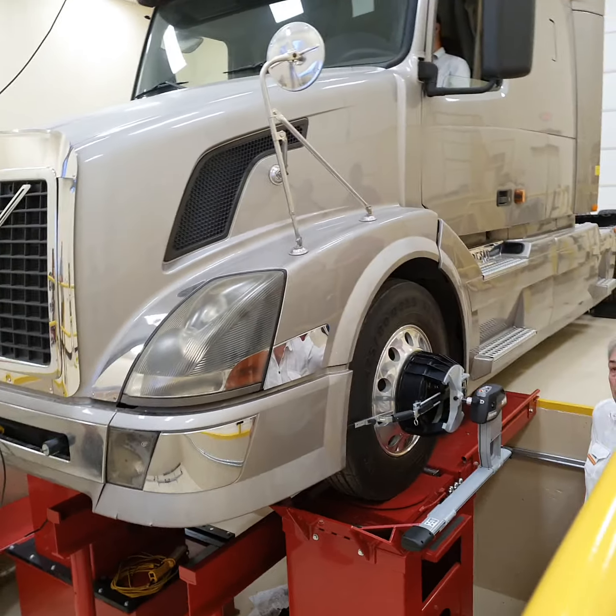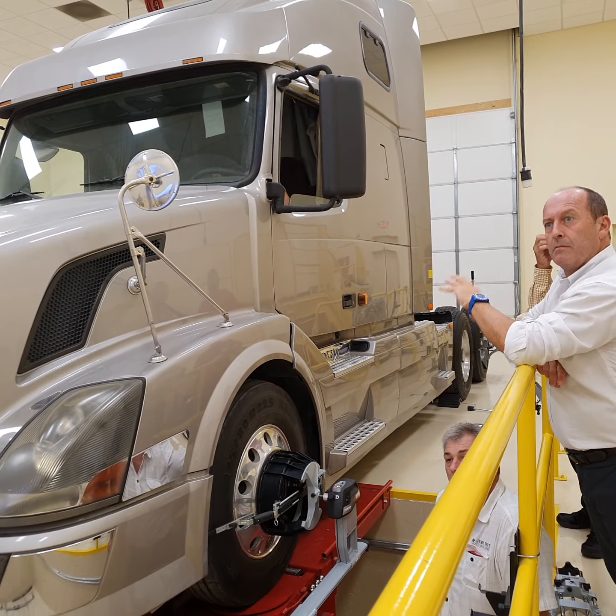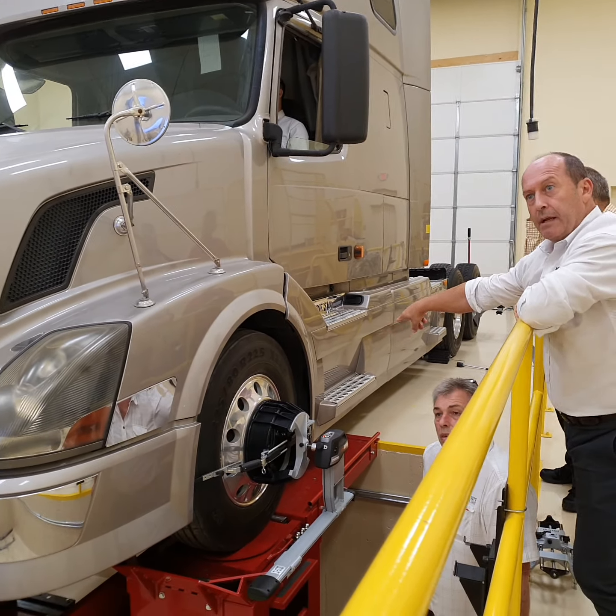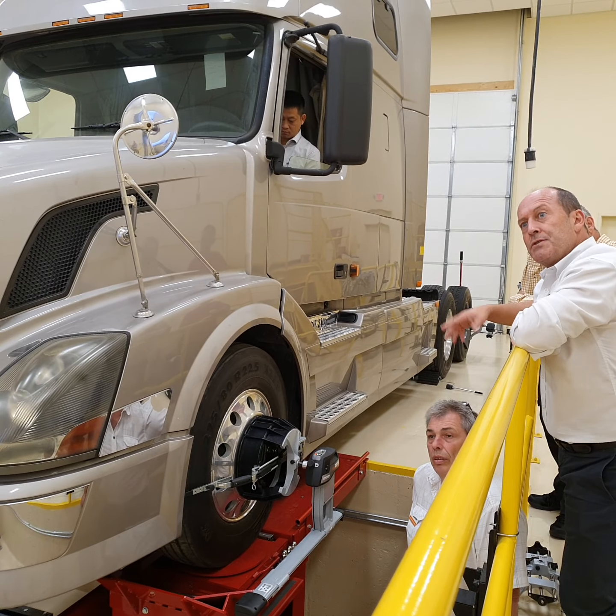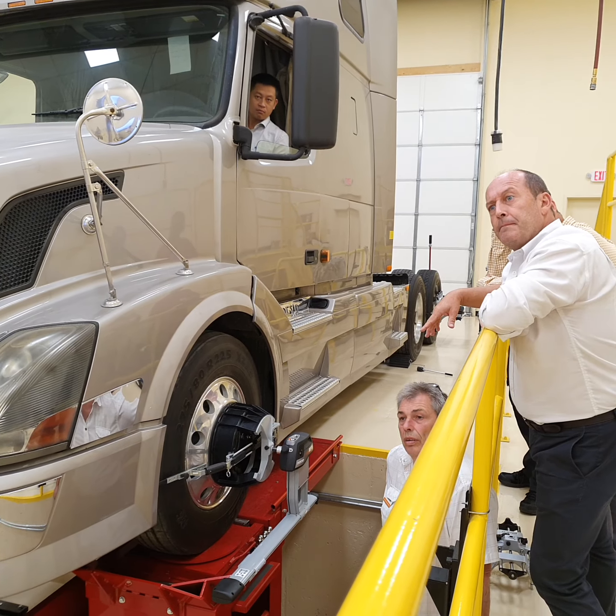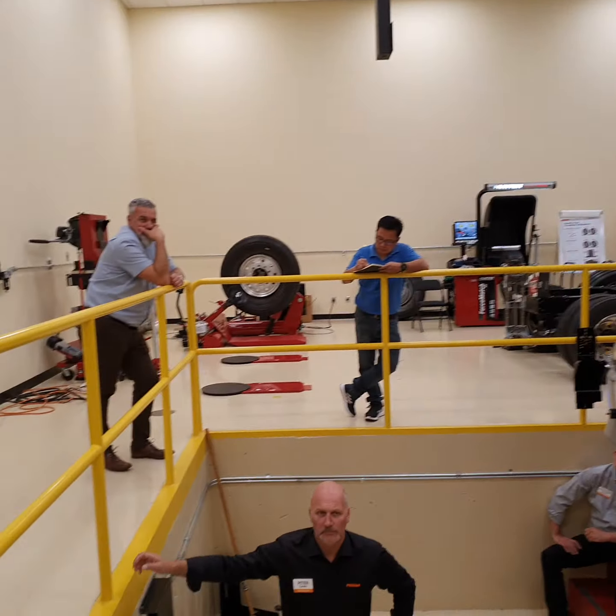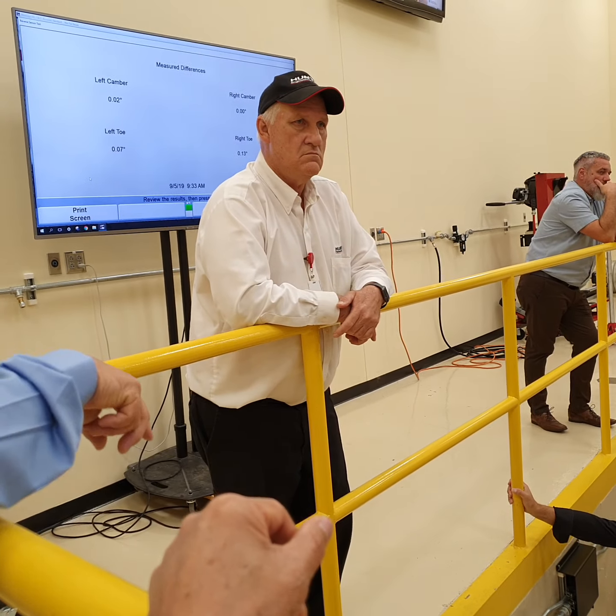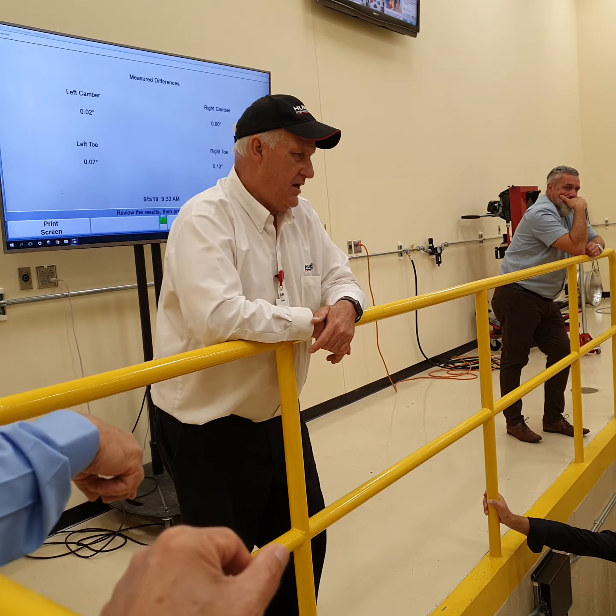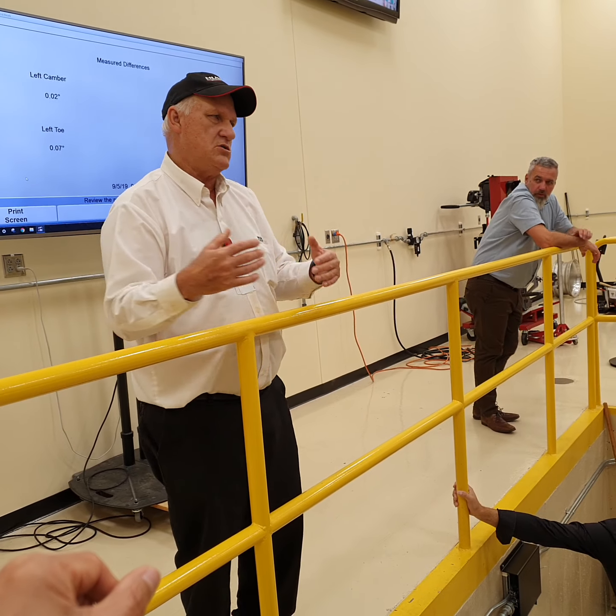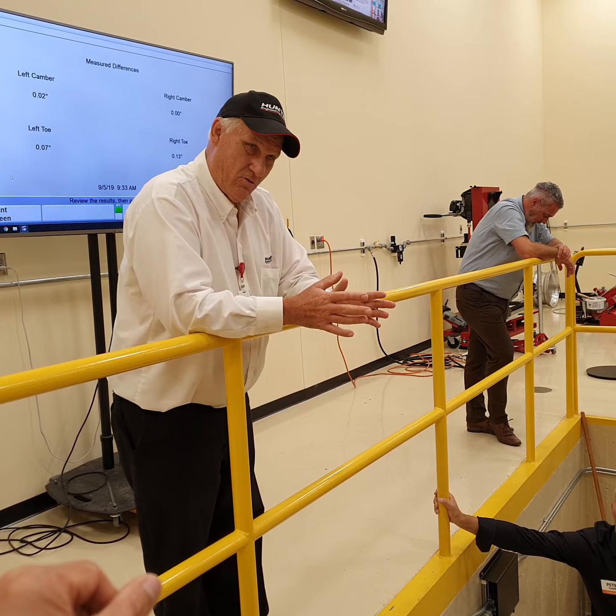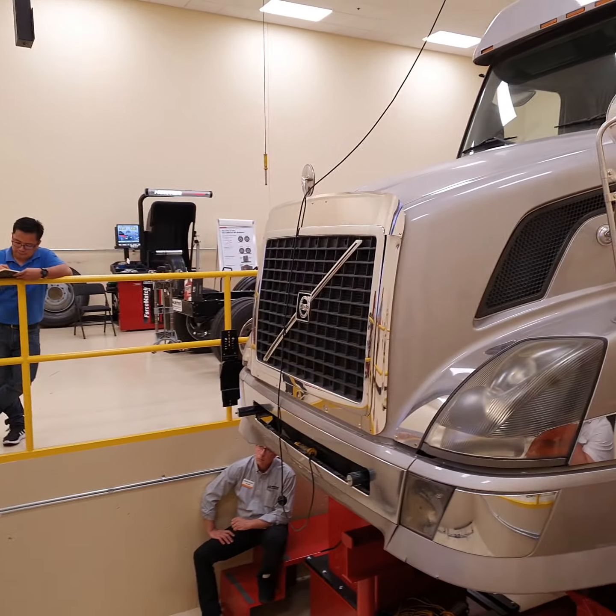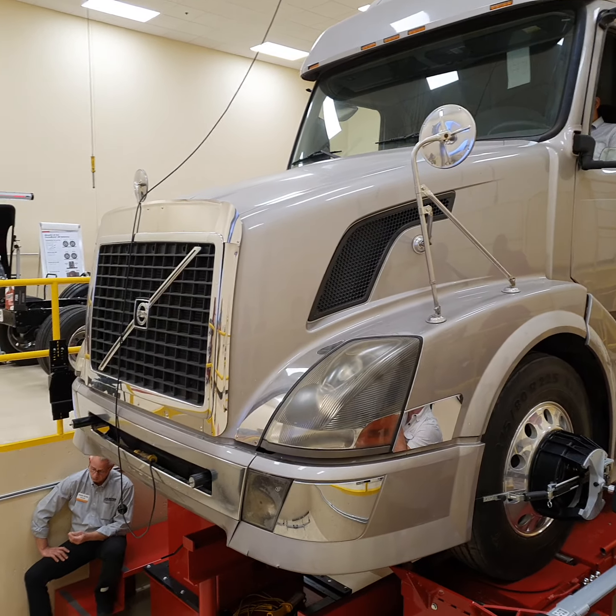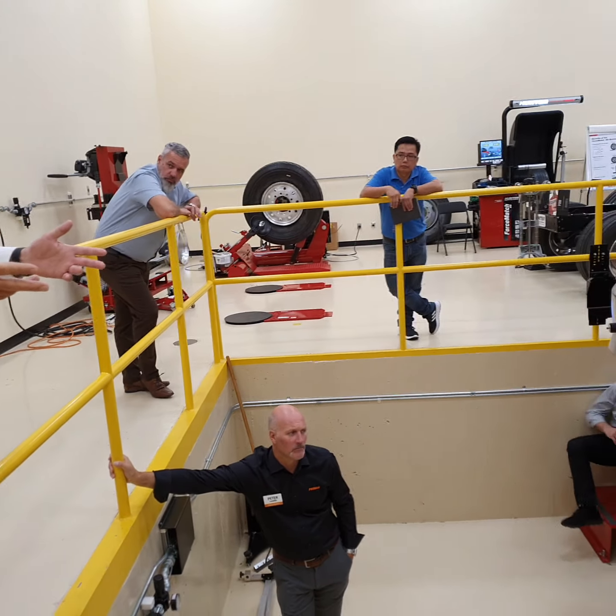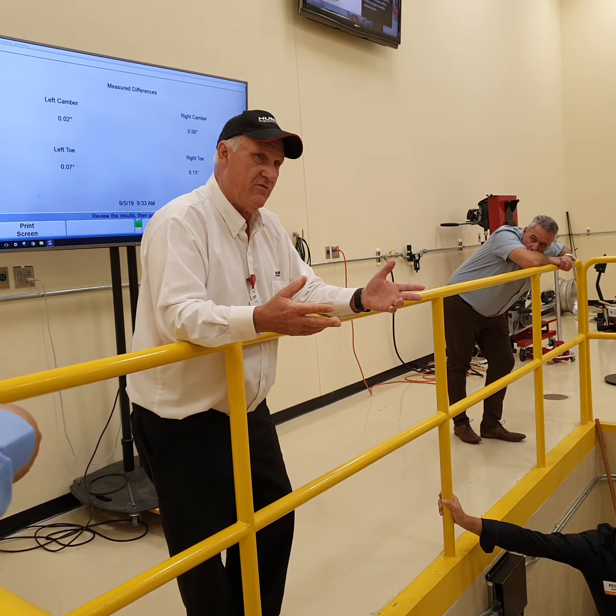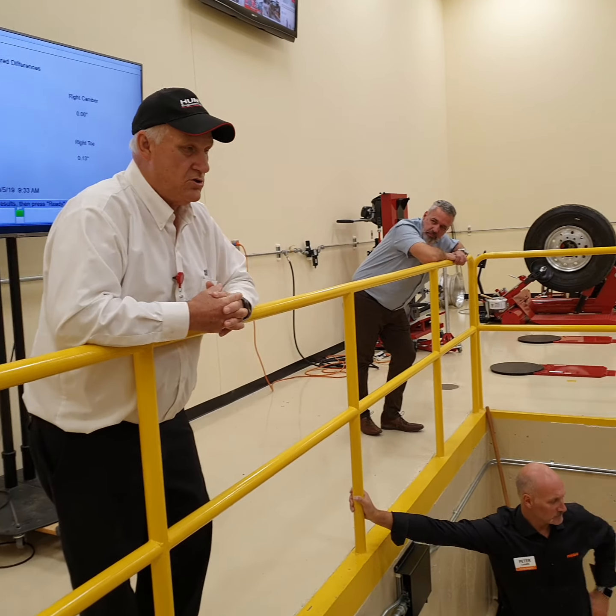Can I see this difference if I do the same with the standard sensor brackets? Or could it be the difference between this quick clamp and the normal clamp? Yes, because the difference will be in how much movement the center hole allows for that shaft. This test should always be done with whatever adapters you are using. If you're using both sets of adapters, I would do the reverse center test with both sets, with these and with the self-centering clamps, because part of the test is the clamp itself. That's part of what you're getting on the measurement.